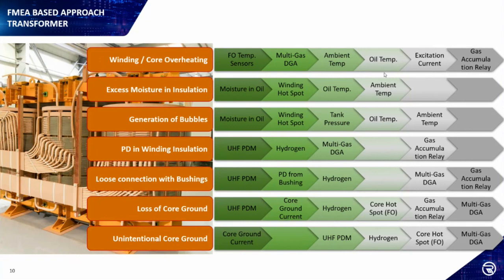So this is another thing our customers need to understand: install the best and optimal sensor on the transformer that gives the failure prediction with sufficient accuracy. And once you get sufficient accuracy, first of all, it reduces the data to analyze, so it reduces the confusion for the operation engineer or maintenance engineer. And the second thing is it reduces the cost of implementing the monitoring system.